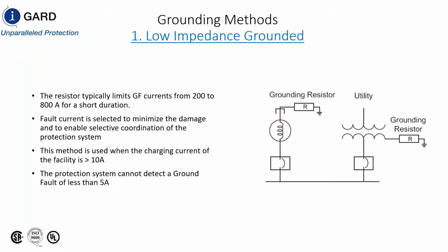So in a low resistance grounded system, the minimum pickup of your protection system determines the level of ground fault current that you want to limit your fault to. So this is why there's always between 200 and 800 amps of ground fault current in a low resistance grounded system. All we need to do is overcome the capacitive charging current. If your capacitive charging current is 20 amps, the next step up is probably going to be 200 or 800 amps, or typically 400 amps, because the minimum pickup of your protection system is going to dictate how low an impedance you can use for a low impedance grounded system.